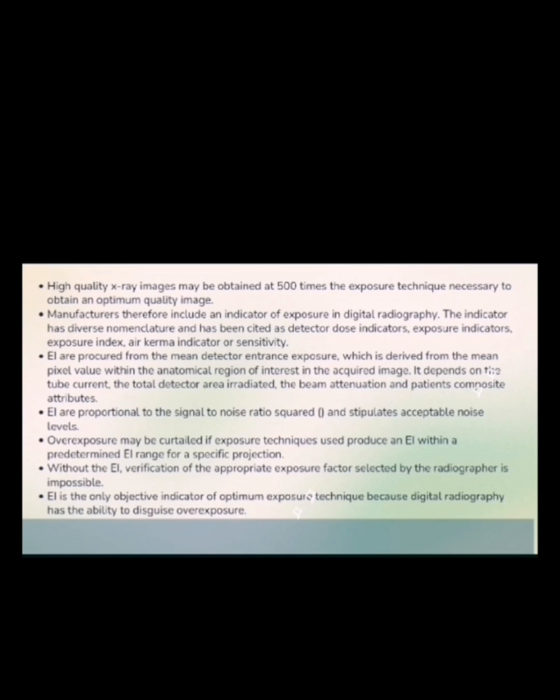Next, the purpose of the exposure indicator is to determine if the optimum exposure technique was used to acquire the X-ray image in digital radiography. It also acts as a safeguard against overexposure in digital radiography and computed radiography. Overexposure may be curtailed if exposure techniques used produce an exposure indicator within a predetermined exposure indicator range for a specific projection.